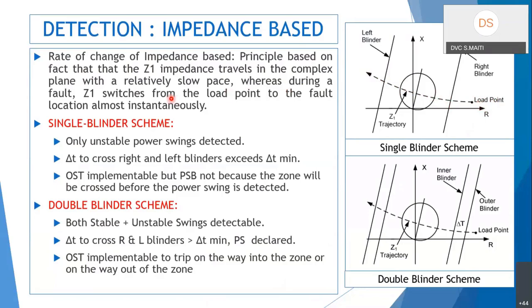For impedance-based power swing detection: in a line relay, the relay is already measuring impedance, so impedance-based detection is the easiest to implement. During a power swing, the positive-sequence impedance Z1 travels in the complex plane at a relatively slow pace, whereas during a fault, Z1 moves from the load point to the fault point almost instantaneously. If the trajectory moves slowly, it is a power swing; if very fast, it is a fault.